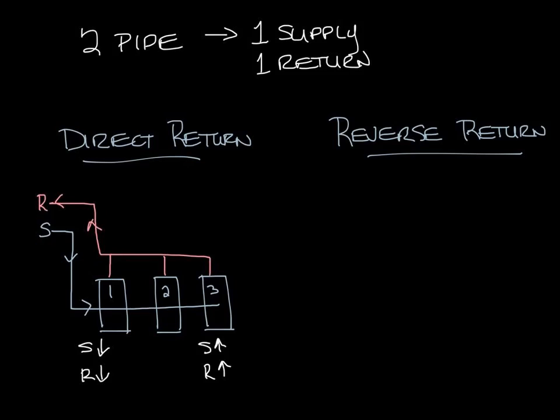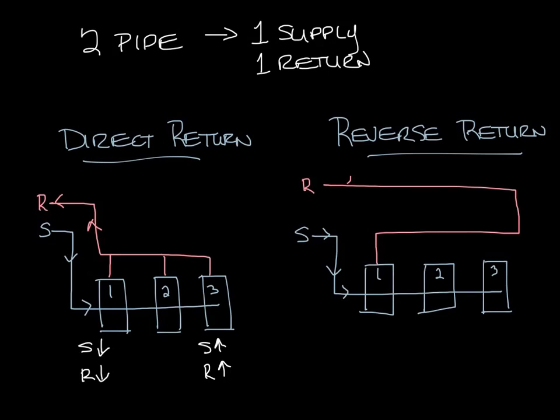In reverse return piping the losses from the supply through the unit and out the return are balanced through the three units. So let's draw our three units again and then let's have our supply that looks the same as it did before coming in through the first unit to the second to the third. But your return looks like this. So the first units return goes the longest, then the second, then the third. So now you can see that the first unit has the shortest supply path but the longest return path. And the last unit has the longest supply path but the shortest return path.